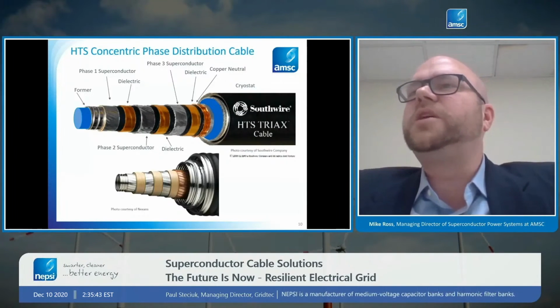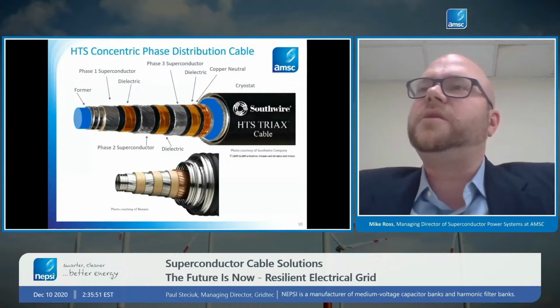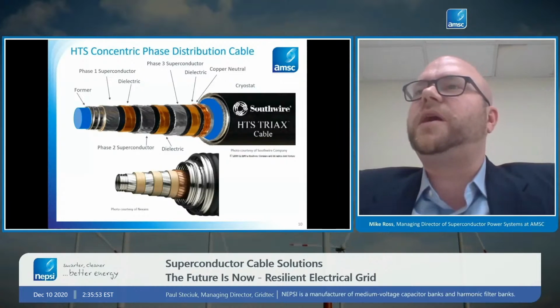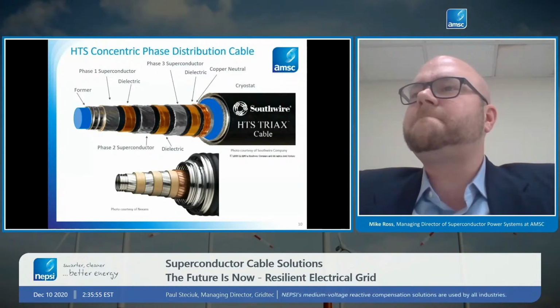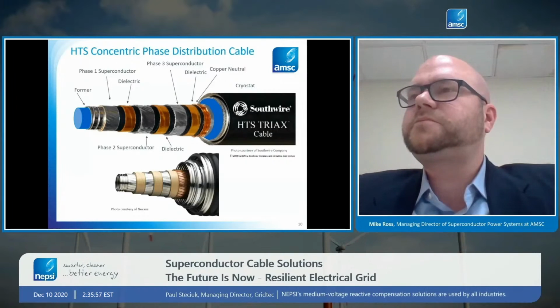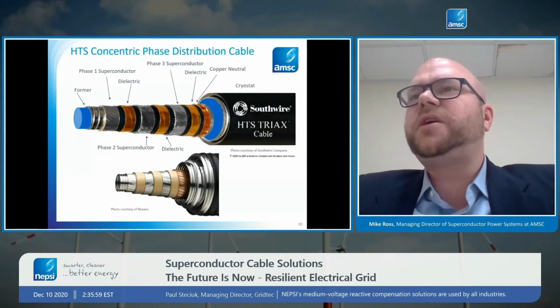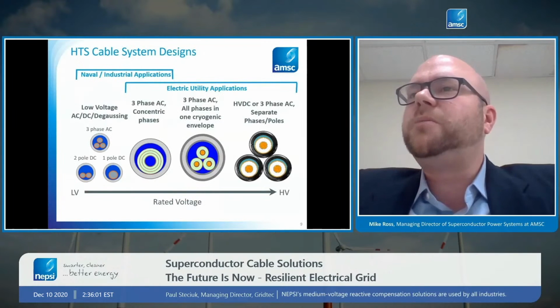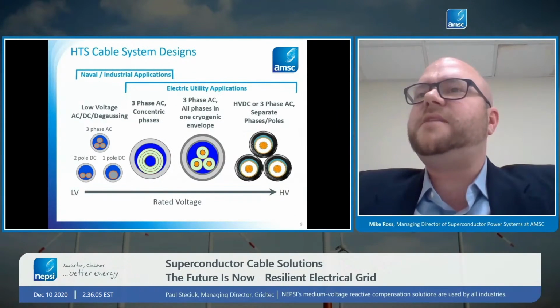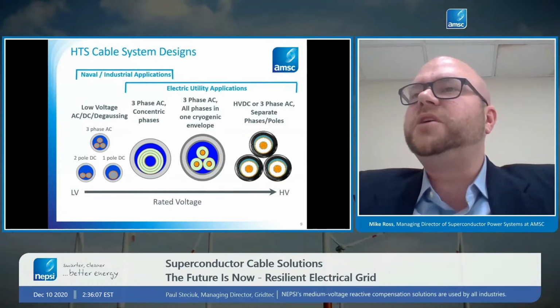And you can see we can run liquid nitrogen down the center of the cable or around the outside of the cable in order to keep it cold while not losing very much heat because of this cryostat on the outside. Hey Mike, what's the voltage of that cable? This particular cable is good up to about 36 kV. When we get beyond 36 kV, we have to move to different designs.